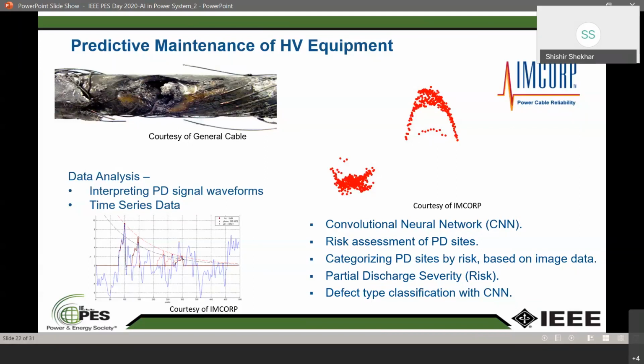If you see on the left hand side, these are the voltage signals that were taken while performing testing of underground cables. Essentially, we took these voltage signal waveforms, which are hundreds and thousands of waveforms, and we ran them through machine learning models. You see the waveforms that are in red. Basically, we used machine learning to identify which of these signals are partial discharge signals. These signals can contain noise. They could have other signal patterns. So you want to detect the right signal pattern, and the signal that we want to use is partial discharge.